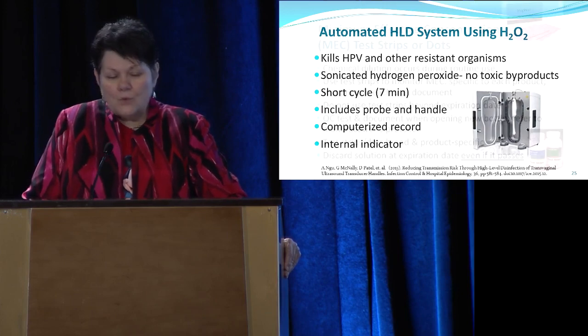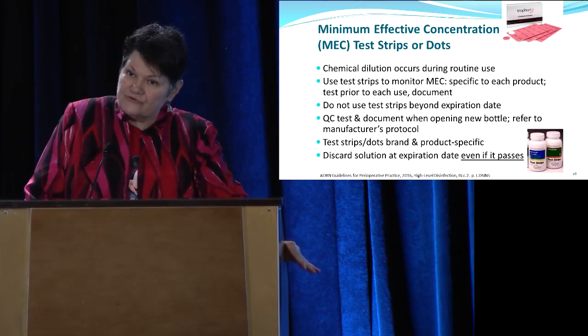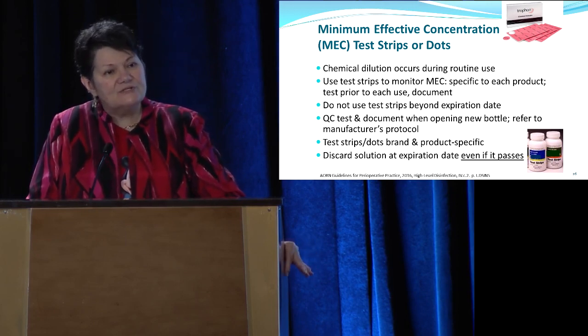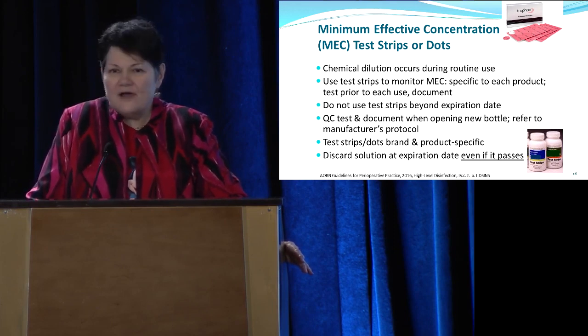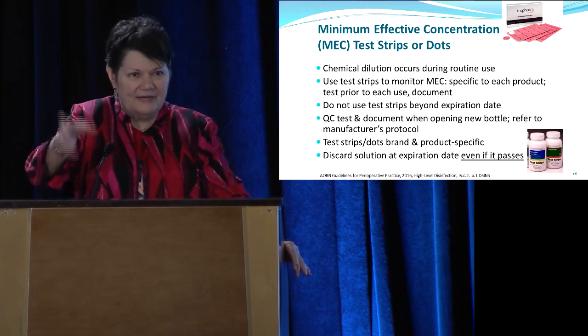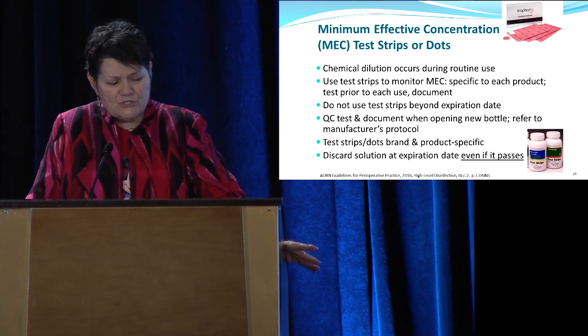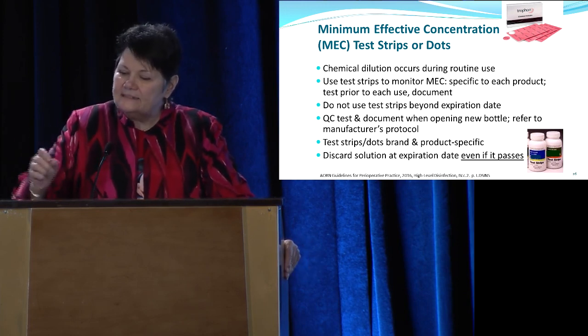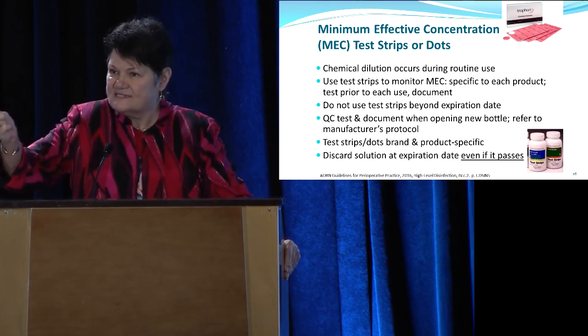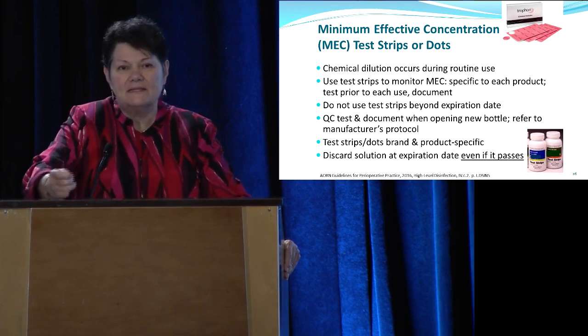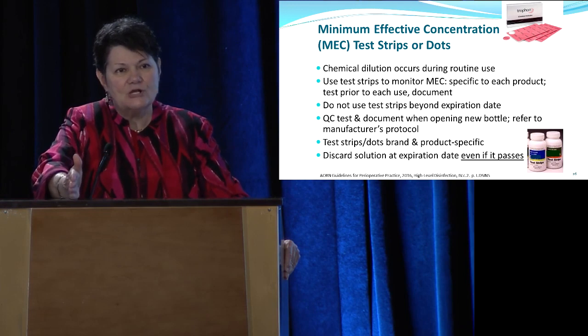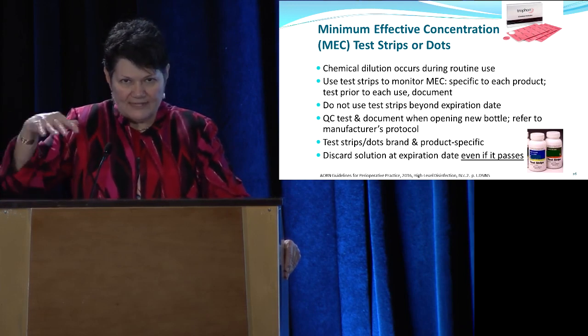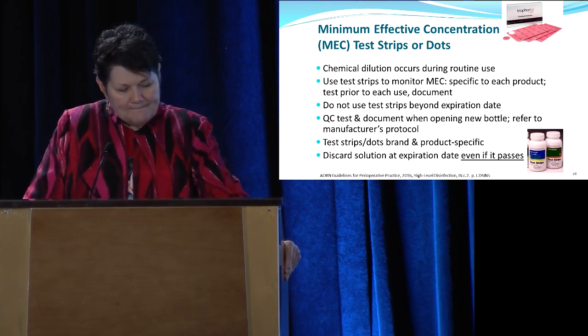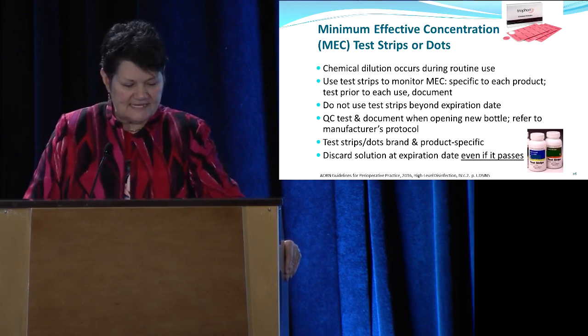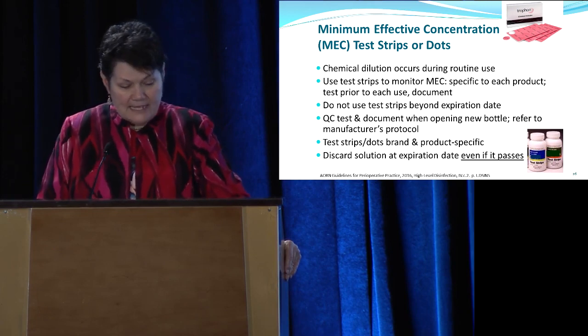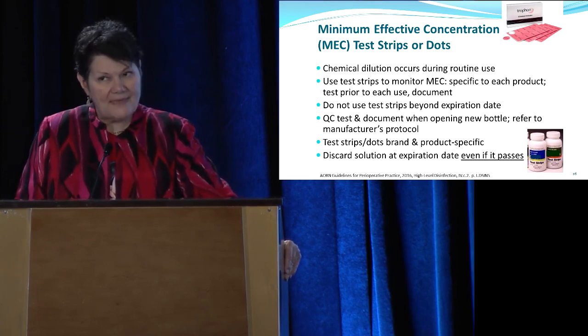So for the minimum effective concentration test strips, or for the Trophon, the dots: the chemicals can get diluted in the soak basins, but with Trophon there is no dilution because there's a fresh cup each time, fresh product each time, which is great. Be sure you're not using your test strips beyond the expiration date, and even if you dip it and it still says pass, if it's past the expiration date, you have to dump it. You cannot keep using it because it passes. So the expiration date is a hard stop, and you need to replace it when you're using glutaraldehyde or OPA or Recert. QC test and document when you're opening a new bottle of the test strips, and you don't have to do that with Trophon. And as I said, discard the solution even if it passes the test.